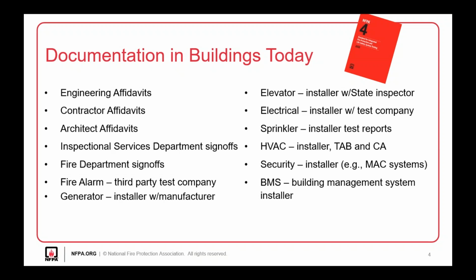All the contractors for each different system, that includes the fire alarm, elevator, electrical, sprinkler, HVAC, security, and BMS systems, they all provide documentation for their own systems. And this documentation certifies that all of the systems have been installed per design. Most, if not all, of the documentation that I've talked about is centered around the specific systems and components within the building. There's no documentation for the building that's showing that all of these systems and components will work together as intended during an event. So this is where the testing and documentation per NFPA 4 starts to come into play.